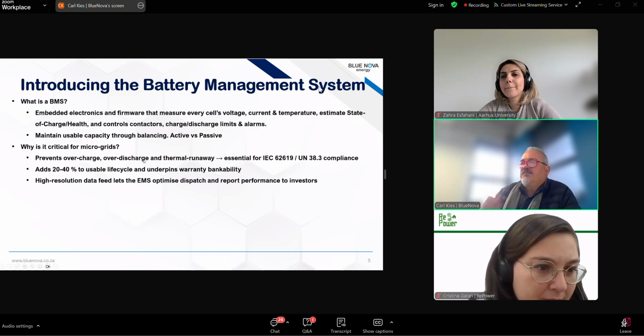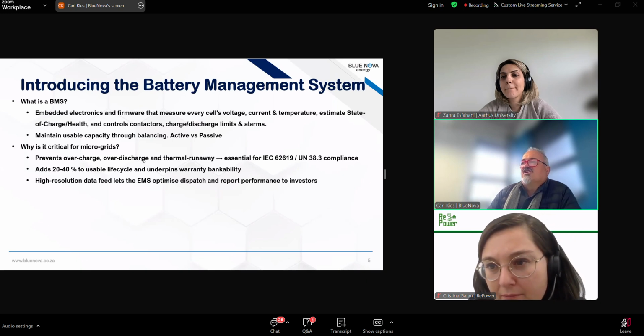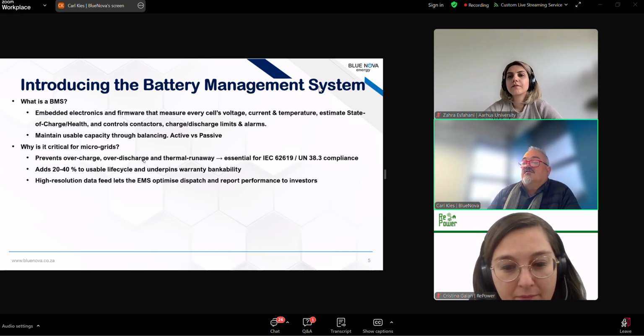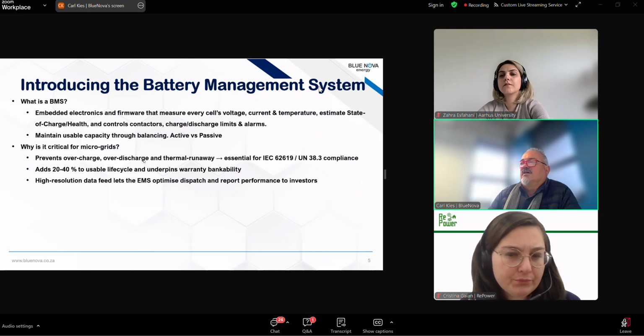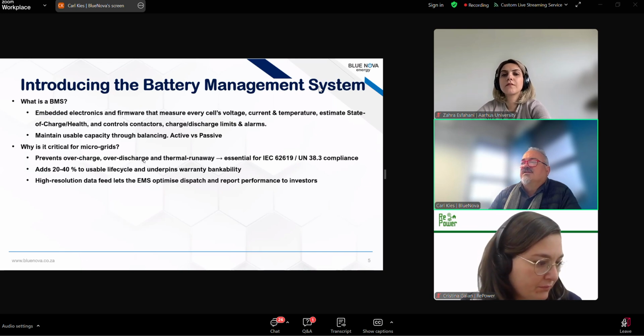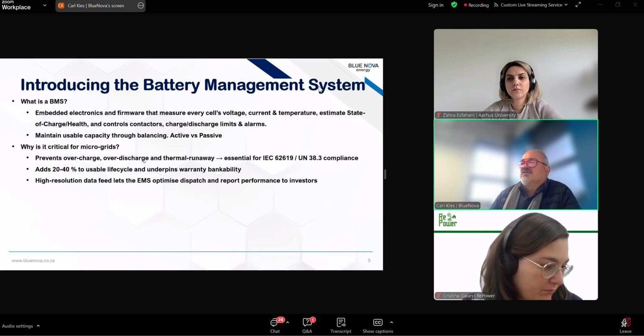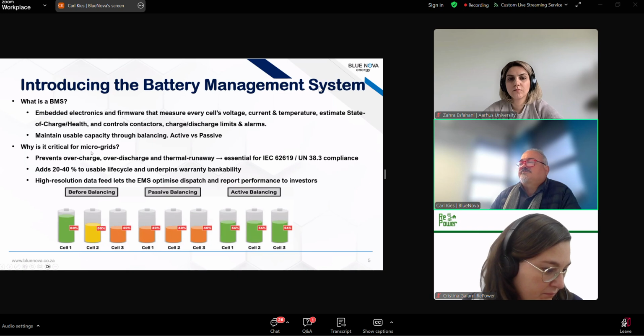Why is this critical? First, it prevents overcharge, over-discharge, and thermal runaway, which is essential from a safety standards point of view. It also adds up to 40% of usable life cycle over the life of the battery, plus it underpins bankable warranties, which is essential from a financing point of view. And it provides high-resolution data to the EMS that can optimize dispatch and report performance to investors.